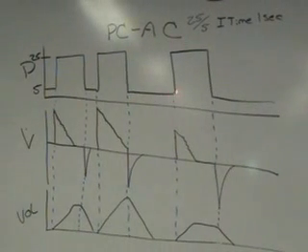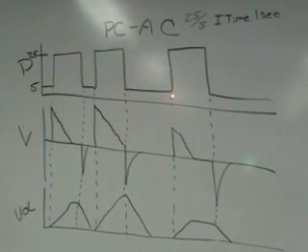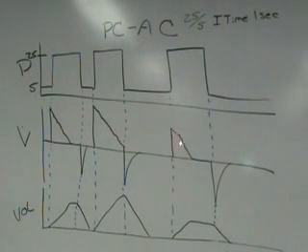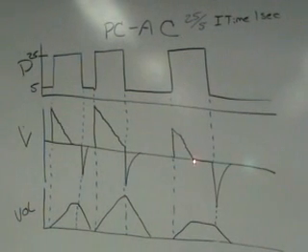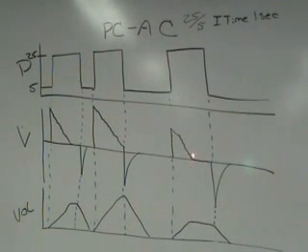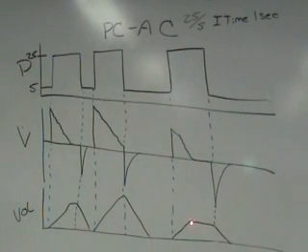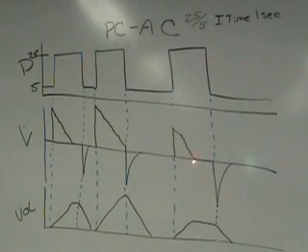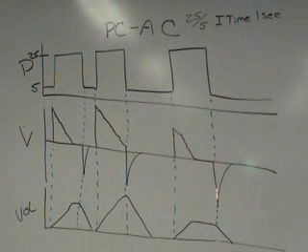My third breath here is essentially the same as my first breath, in which it's a time-triggered breath. It goes to the pressure level for the set I time. The flow rate rapidly decelerates to 0, showing that my alveolar pressure must be at my pressure control level at this point. My alveolar pressure is at 25 right here, and therefore the volume that's being delivered has already been delivered at that point during the inspiratory cycle. The pressure stays at that level, the volume stays in until the end of the I time and the patient exhales. So that'd be the technical description of it.